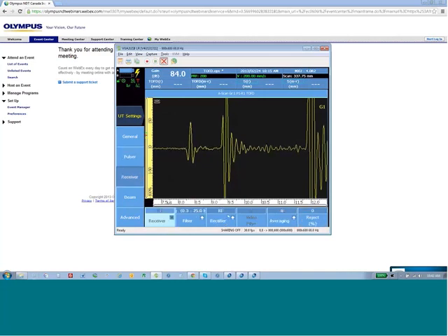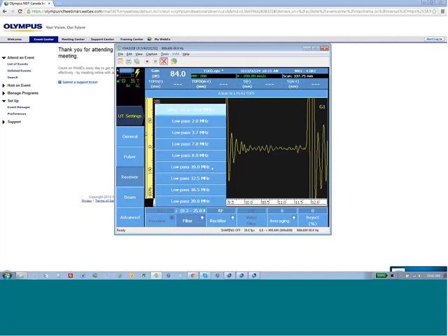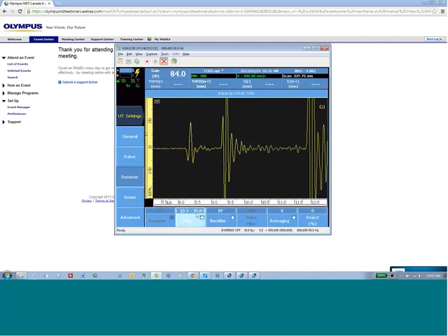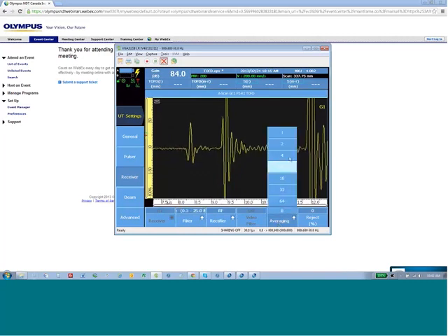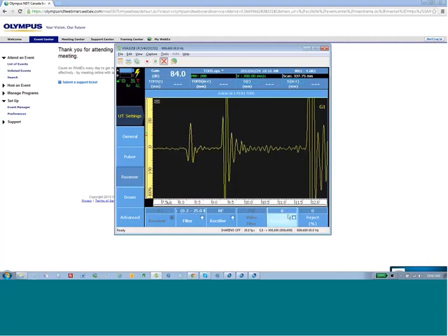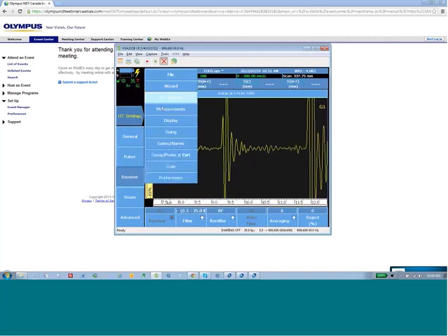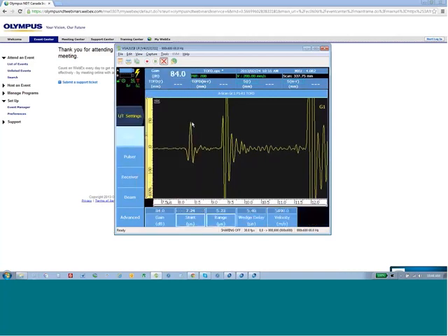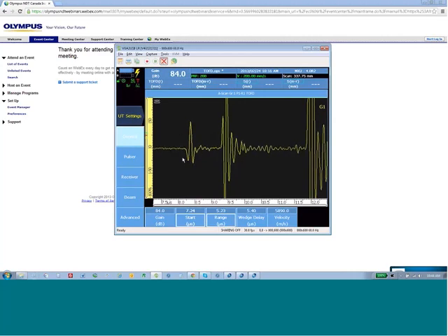We select the receiver, select the filter frequency that produces the best results — including no filter if results are better — and experiment with the averaging. More than necessary isn't going to help and will slow acquisition. When setting our initial inspection sensitivity, we typically want the lateral wave set somewhere between 40% and 80% depending on the code. We ensure the back wall is not saturated, and that the range is properly set. Calibration is taken care of in inspection or analysis mode.